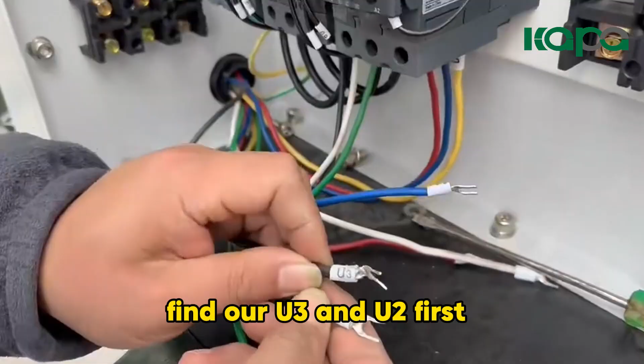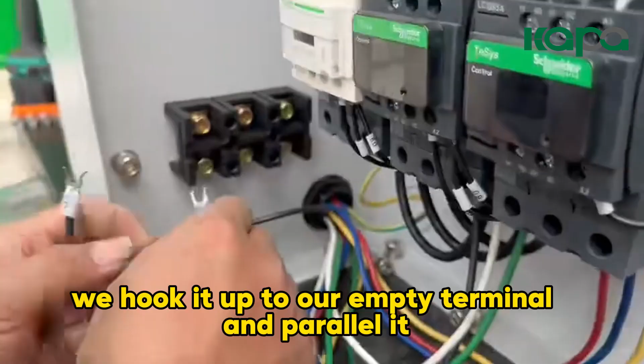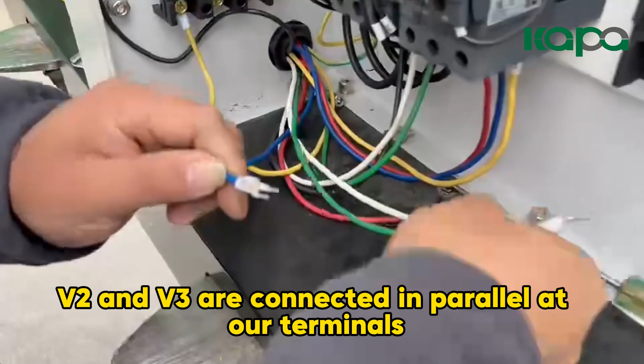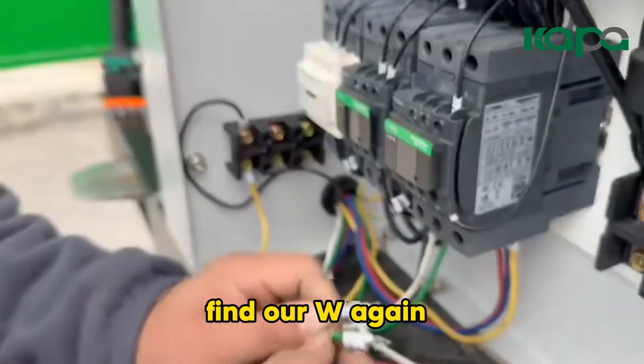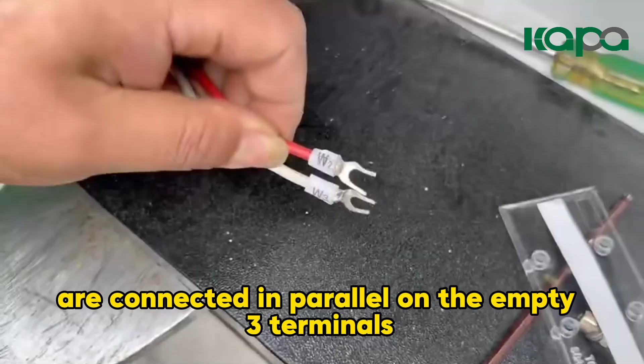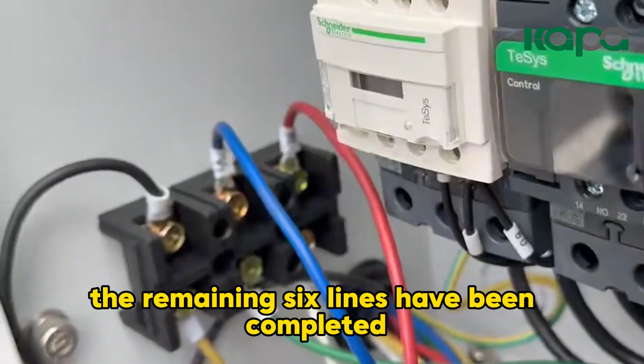At this time, find our U3 and U2 first. We hook them up to our empty terminal and connect them in parallel. Let our U2 and U3 terminals be connected in parallel. Alright, find our V again. V2 and V3 are connected in parallel at our terminals. Find our W again. W2 and W3 are connected in parallel on the empty terminals. Okay, at this time, let's check what you just received. U2 and U3 are connected in parallel, V2 in parallel with V3, W3 parallel to W2. Okay, at this point, the remaining 6 lines have been completed. Then let's check again, review it.